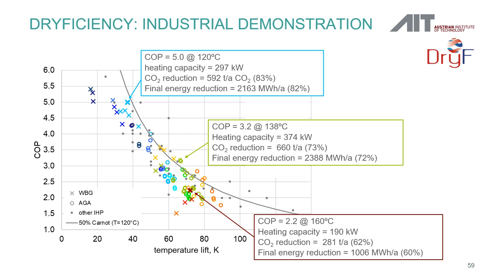When we go to lower temperature lifts, so this is basically lower supply temperatures when we keep the source temperature constant, we have at a supply temperature of 120 degrees C a COP of 5, which is very attractive. And then we have also very high CO2 emission reductions and final energy reductions in the range of about 80%. So this demonstration of the high temperature heat pump was very successful, and it also showed the benefits for industrial companies to integrate a heat pump in their process and to make use of the waste heat that is otherwise just released into the environment.